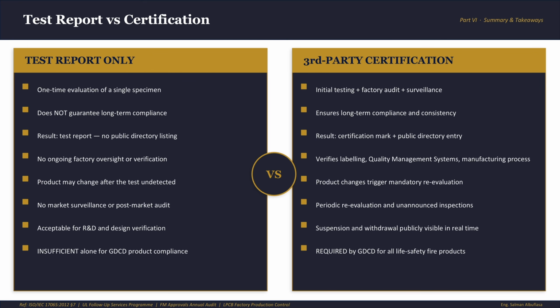So technically, a test report is only acceptable for research and development (R&D) or for early stage design verification. And there are very explicit scenarios where the authority having jurisdiction might accept a test report only. What is not enough on its own for any life safety products does not prove anything. While third-party certification goes much further than that, it means an accredited organization has reviewed the manufacturing process and determined that the product complies with the specific standards, which includes formulations and materials, reviews, testing, and facility inspection. All of that is certification.